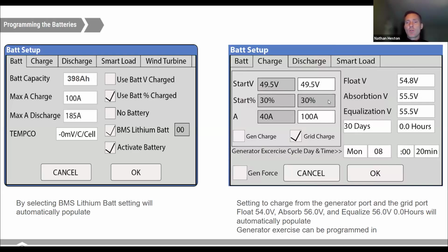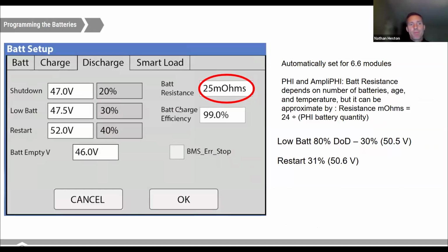And provide that starting. If you're trying to test out your system and you've done your settings and you want to test out your generator, you can click this box for force gen and then click OK. That will automatically start up the generator. You can uncheck the box, click OK again, and it'll stop the generator. So you can test your two-wire start that way.